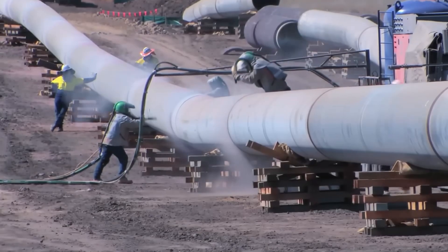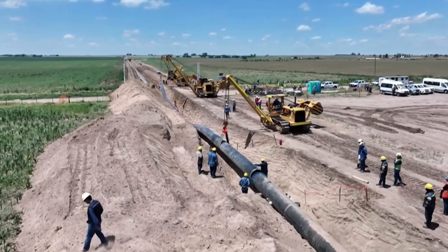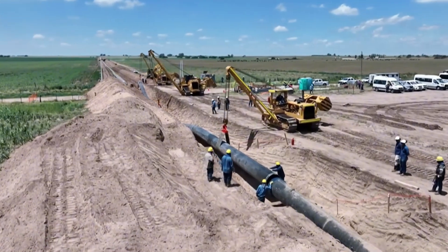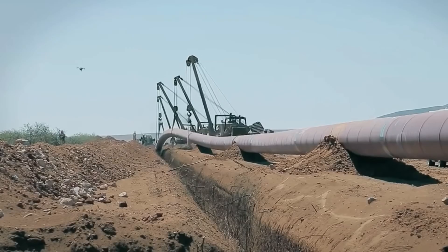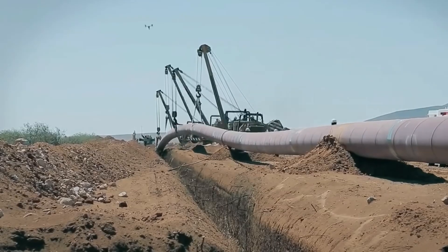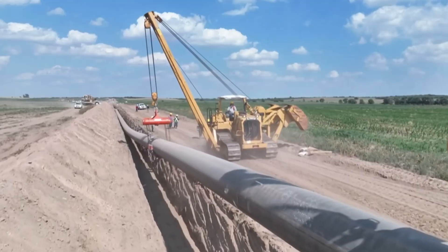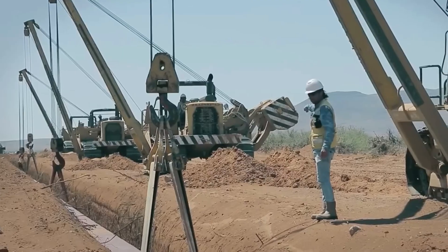The pipe walls are coated with multiple protective layers. The inner layer uses materials specifically designed for drinking water, preventing metal contamination and reducing scale buildup. The outer layer resists corrosion and endures sand, wind, salt, and ground temperatures that can exceed 60 degrees Celsius. In many sections, the pipes are buried deep under the sand to reduce heat, impact, and protect against mechanical damage.